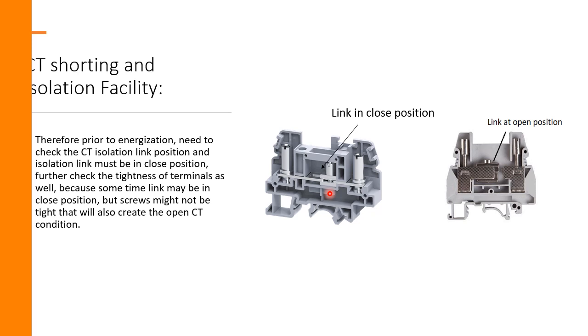Looseness is basically high burden — sparking is created. The condition is just like near to CT open condition, which is also hazardous.